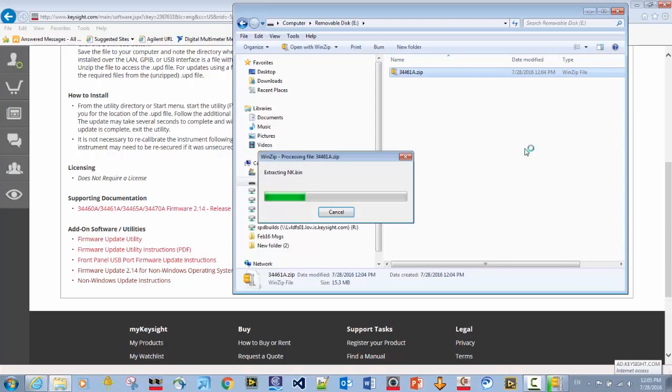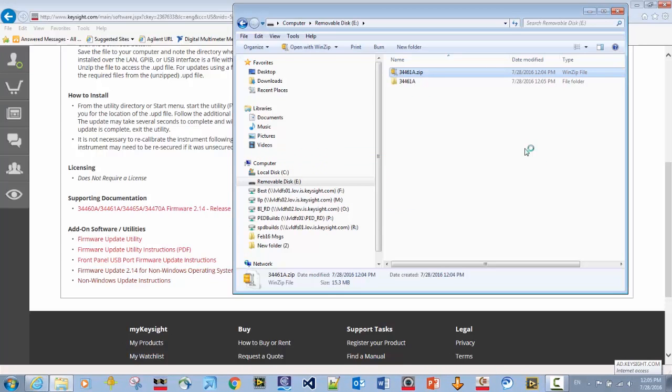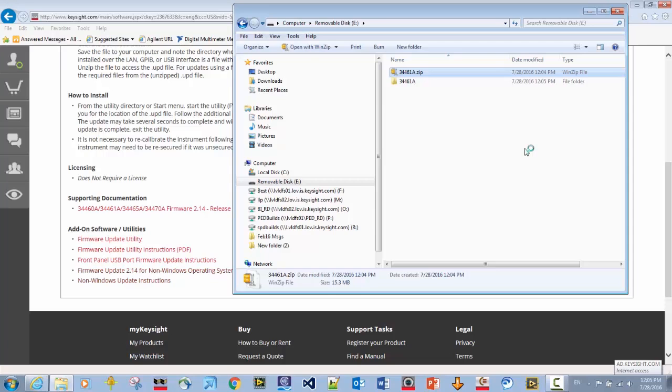A key thing to keep in mind here is that the firmware update file applies to four different DMMs. It applies to the 34460, 61, 65, and 70. However, when updating from the USB thumb drive, you want the files within a folder that's titled 34461A. That's the file name. Regardless of the instrument model number that you are updating, the firmware will recognize which particular instrument is involved and update the firmware accordingly. But again, the file has to be named 34461A.